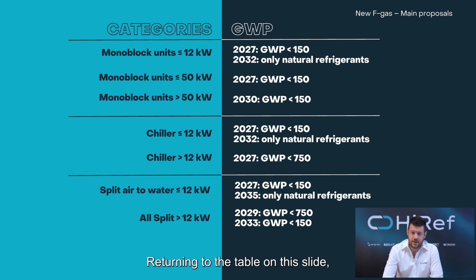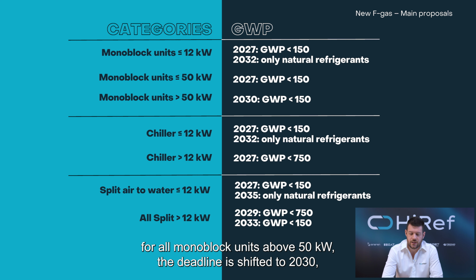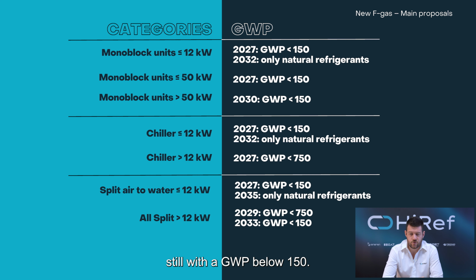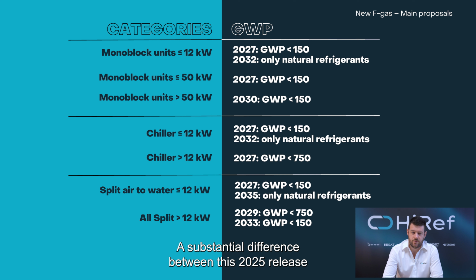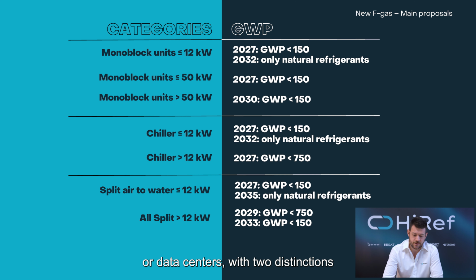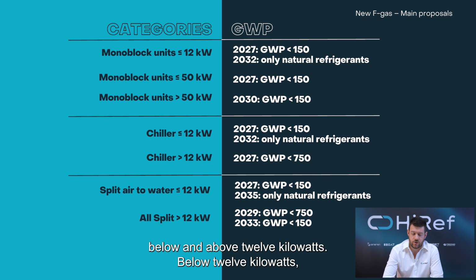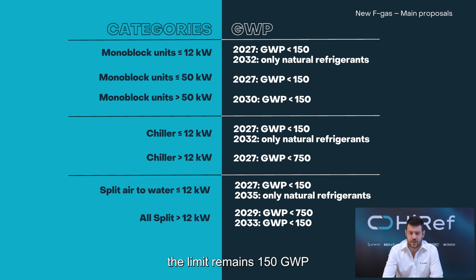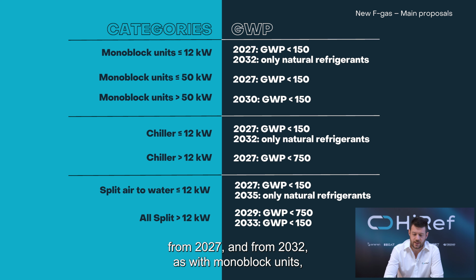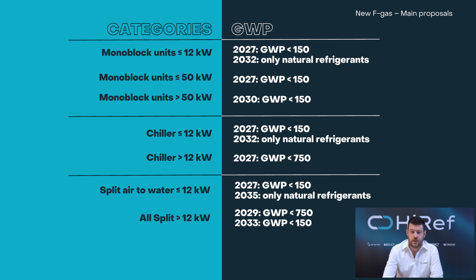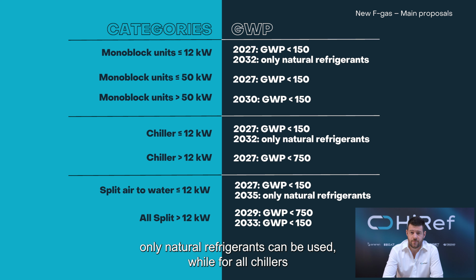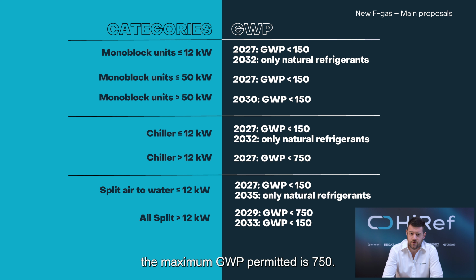Returning to the table on this slide, for all monoblock units above 50 kW, the deadline is shifted to 2030, still with a GWP below 150. A substantial difference between this 2025 release and the previous one is the distinction for chiller units producing only chilled water, for example for industrial sectors or data centers, with two distinctions, below and above 12 kW. Below 12 kW, the limit remains a GWP of 150 from 2027, and from 2032, as with monoblock units, only natural refrigerants can be used, while for chillers above 12 kW, the deadline is still 2027, but the maximum GWP permitted is 750.